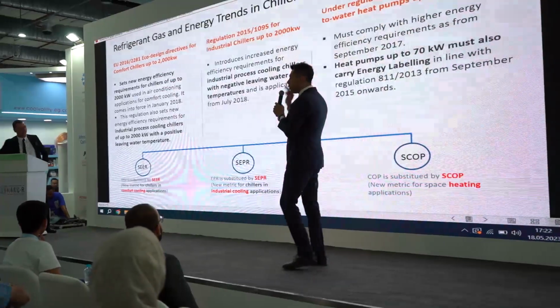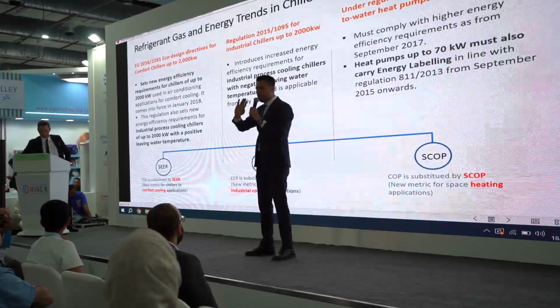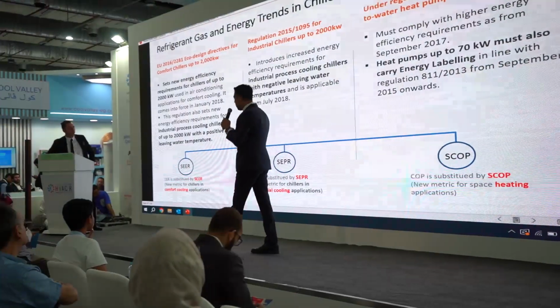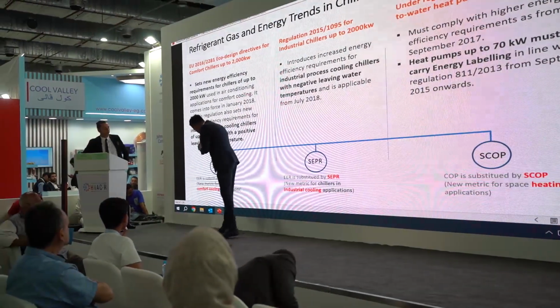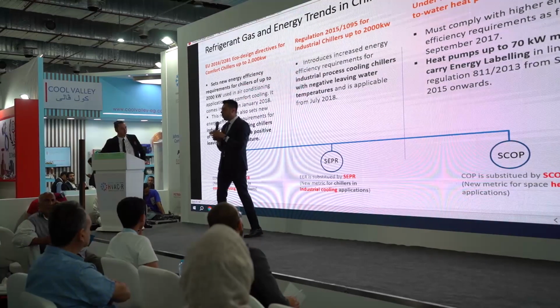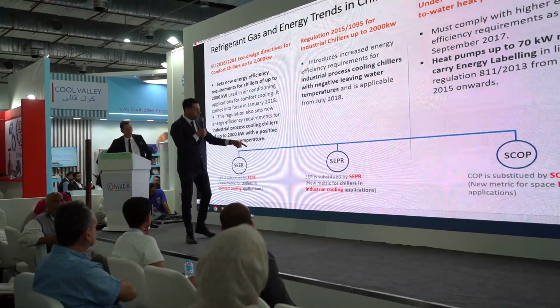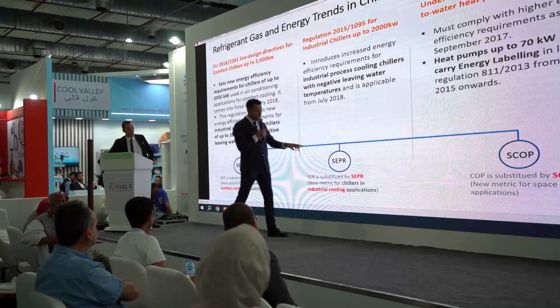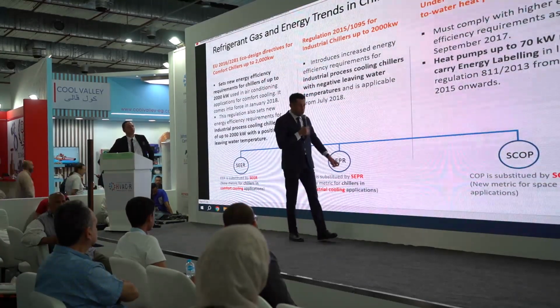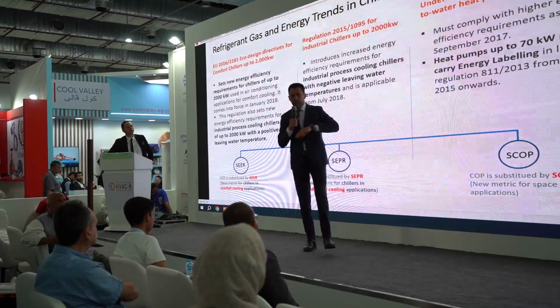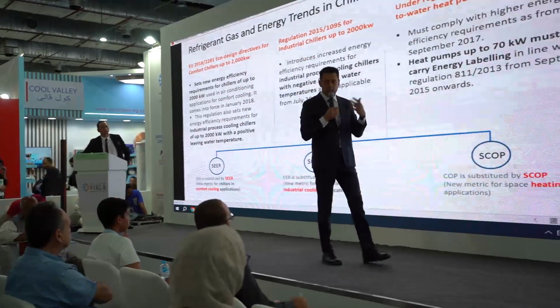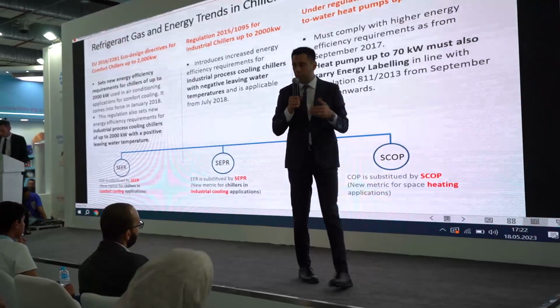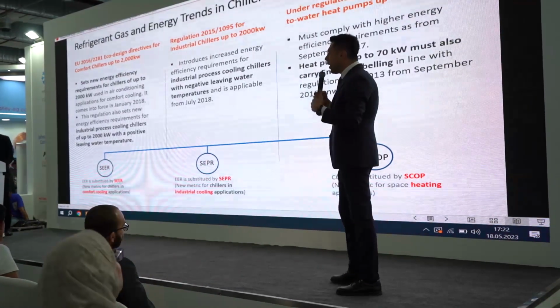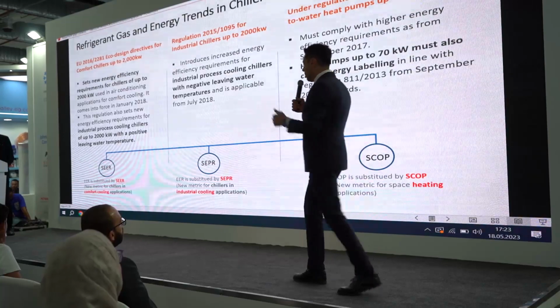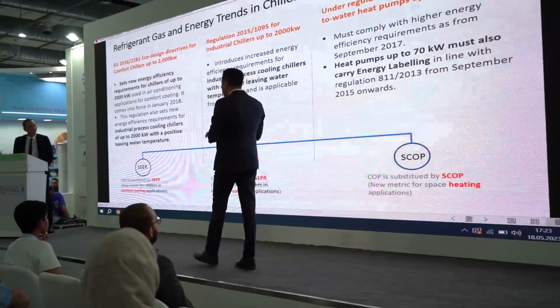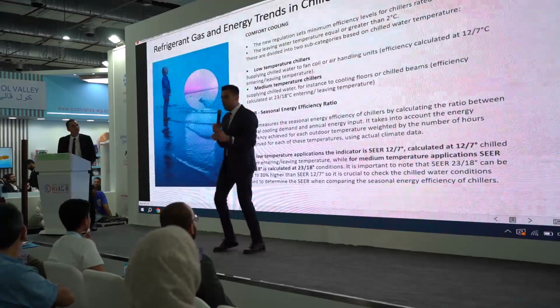So what they did, today there is no EER. EER is passed away. But today we have to be speaking about the seasonal energy efficiency, SEER, for the comfort cooling. Comfort chillers simply. For industrial chillers, the new designation is seasonal energy performance ratio. So process chillers, they are working in different conditions. 7-12, they are totally different conditions. Sometimes glycol is used because they need year-round cooling. So different seasonal energy efficiency is coming into force.